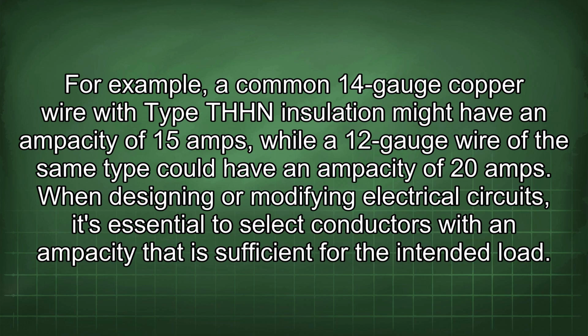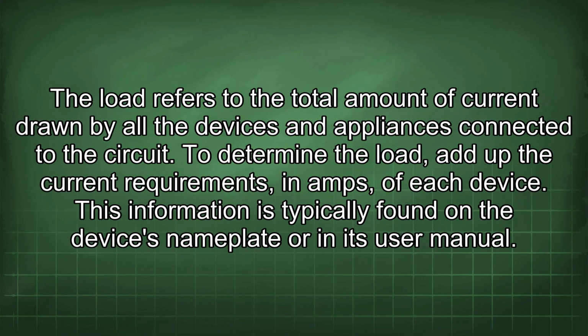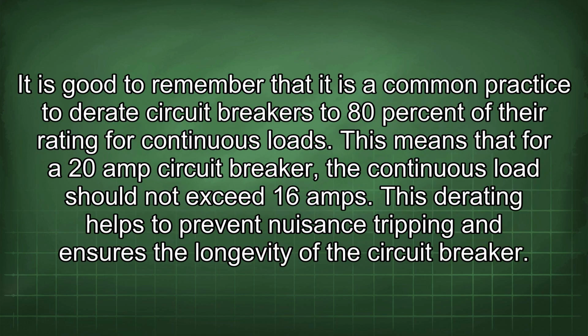When designing or modifying electrical circuits, it's essential to select conductors with an ampacity that is sufficient for the intended load. The load refers to the total amount of current drawn by all the devices and appliances connected to the circuit. To determine the load, add up the current requirements in amps of each device. This information is typically found on the device's nameplate or in its user manual. It is good to remember that it is common practice to derate circuit breakers to 80% of their rating for continuous loads. This means that for a 20 amp circuit breaker, the continuous load should not exceed 16 amps. This derating helps to prevent nuisance tripping and ensures the longevity of the circuit breaker.